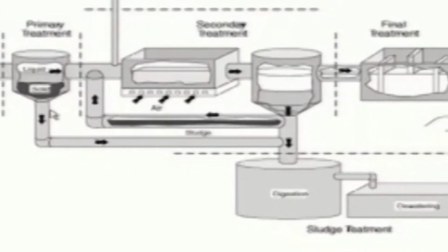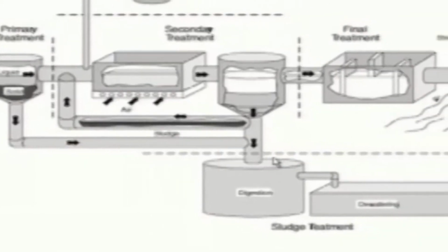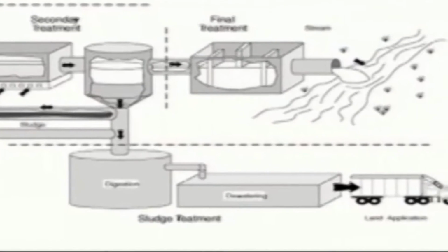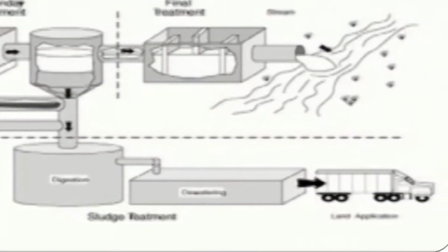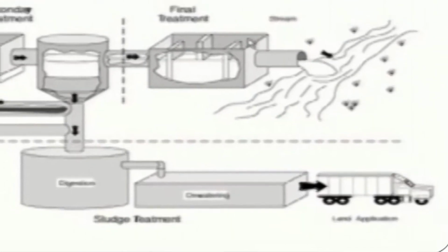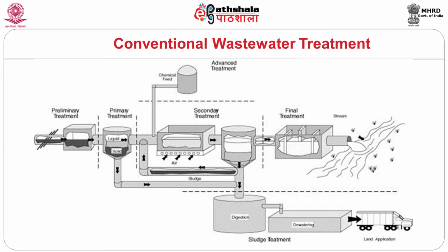Subsequently, we collect primary solids as well as secondary solids with the aid of a sludge withdrawal facility, and it can be thickened. Further, it can be digested with the aid of an anaerobic facility. Anaerobically digested sludge can be further dewatered and it is safe for disposal. The secondary clarified effluent can be further treated by adopting a disinfection facility and it can be let out into the water environment after attaining the stringent State PCB standard.